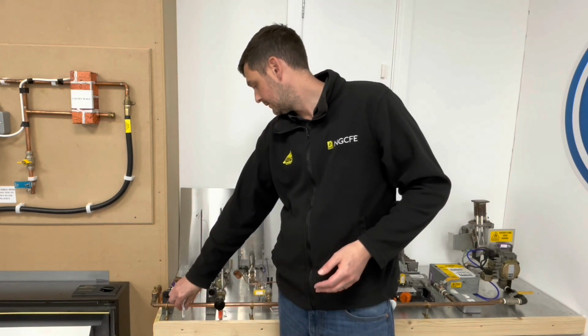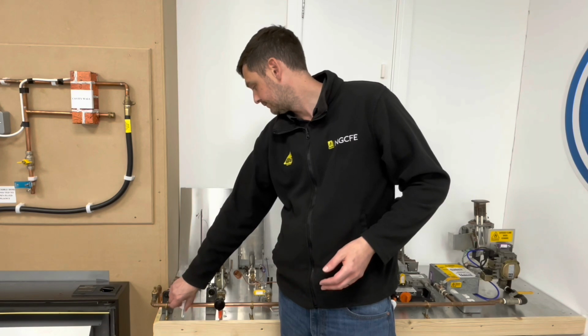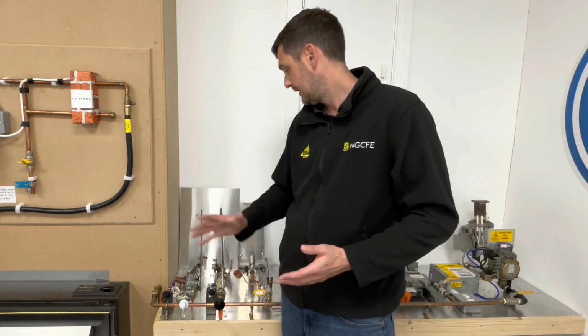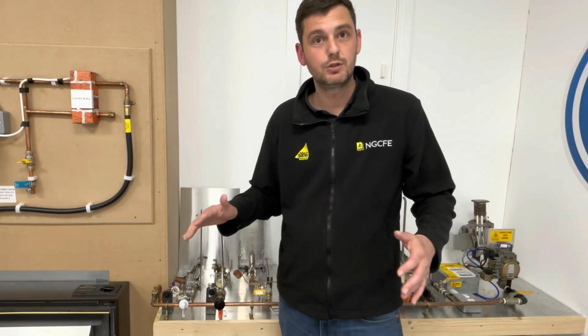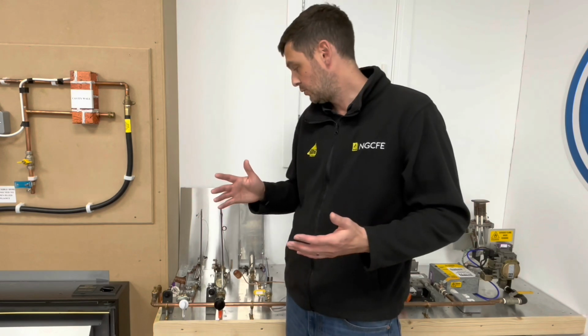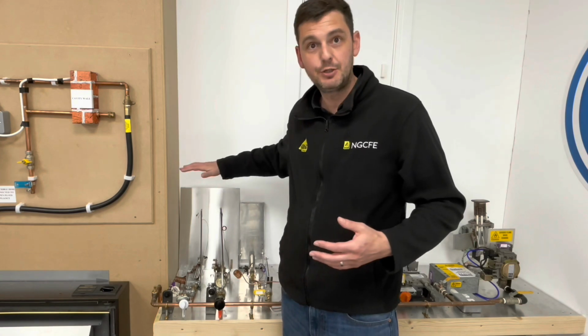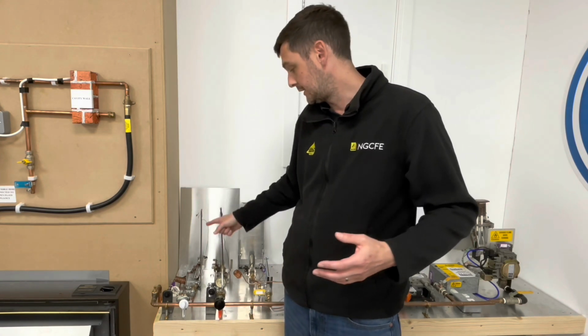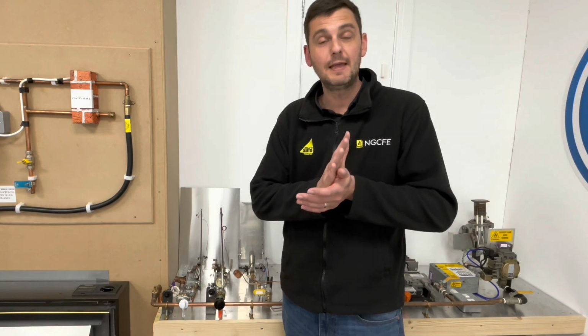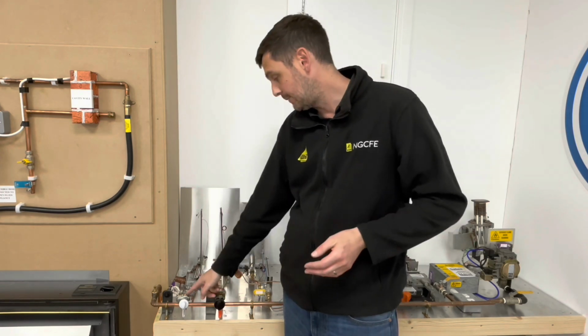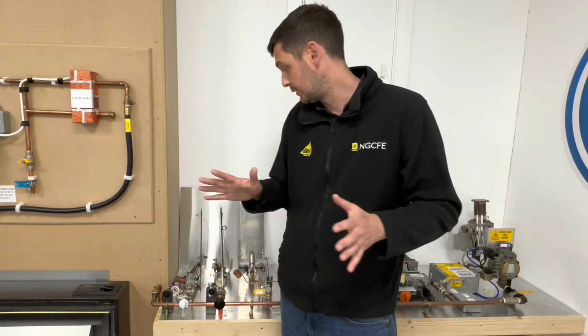So, potential faults on this setup is that once the appliance reaches temperature, the flame goes out and it's extinguished. So if that happened, it would be because when the thermostat's got to temperature, because the oven's hot enough and the vapour has expanded and closed the bellows, if the flame goes out completely, it's because the little bypass that allows that little bit of gas through to keep the burner lit on low flame is blocked. So there's no way of gas getting to the burner, so the flame's extinguished.